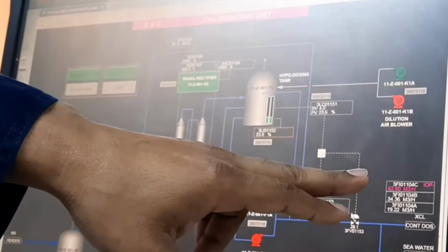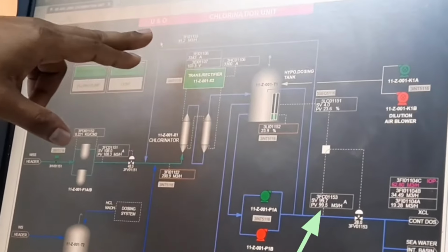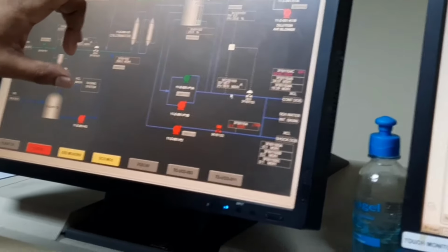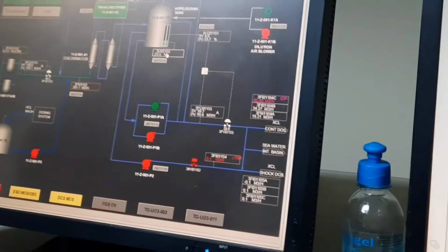We are discharging 99.7 meter cube as continuous dosing, and 99 meter cube as circulation flow. So around 198.7 meter cube we are discharging, but we are storing 207 meter cube. The remaining 8.3 meter cube per hour accumulates. If 8.3 meter cube per hour accumulates, then in 8 hours it will come to 66.4 meter cube.